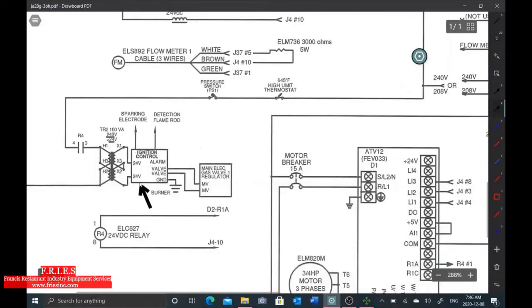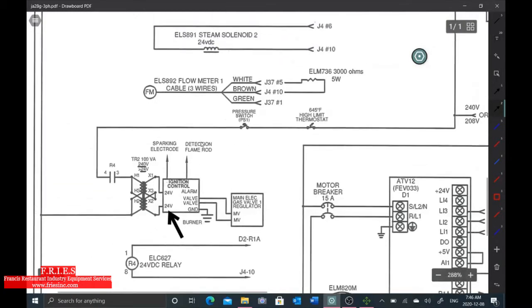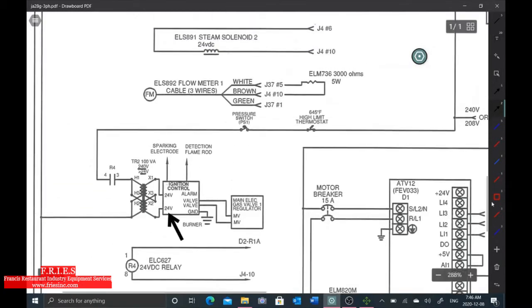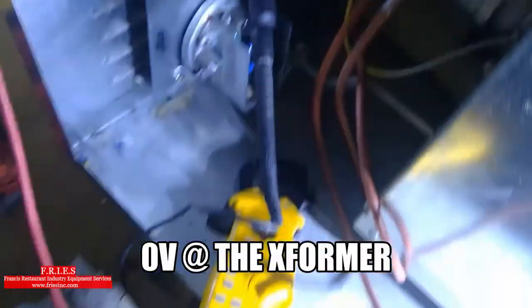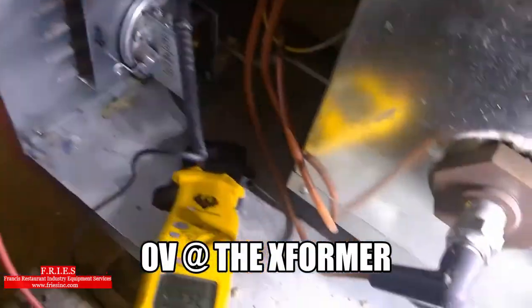Alright, I do not have voltage here at my module. So what I'm going to do is work backwards, okay? Because it's an intermittent problem, I have to work very quickly. So these are the steps I'm going to take. I'm going to test the incoming power to this transformer, so the primary side. If there's no power here, I'm going to work backwards. Alright, I'm testing the primary side of the transformer. I have 0 volts there.